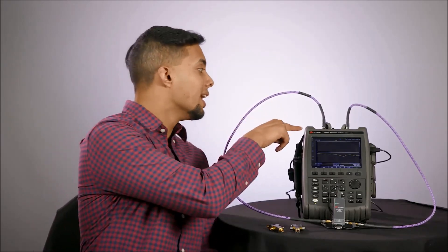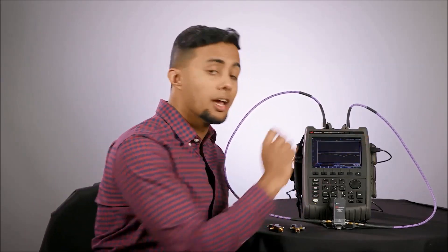So, for a full two port calibration with e-CAL, we simply connect the e-CAL module to ports one and two, and connect the USB cable to one of FieldFox's USB ports to provide power to the e-CAL module. Connection is that fast, and we are ready to set up the calibration.